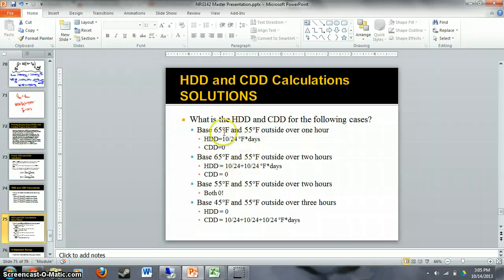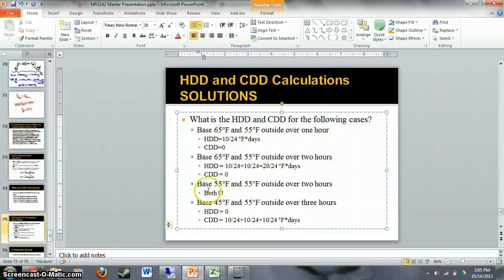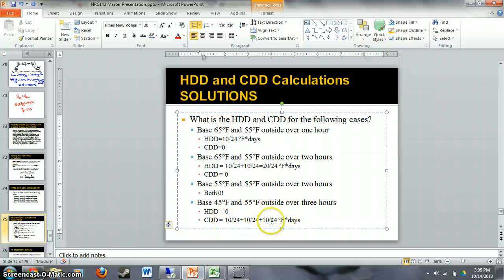If we have a base of 65°F and 55°F outside over two hours, we do the same calculation twice and add them: 10/24 plus 10/24 equals 20/24 heating degree days. If the base is 55°F and it's 55°F outside, both heating and cooling degree days are zero since the numerator is zero. If the base is 45°F and it's 55°F outside, we get three hours of cooling degree days totaling 30/24, and heating degree days is zero.